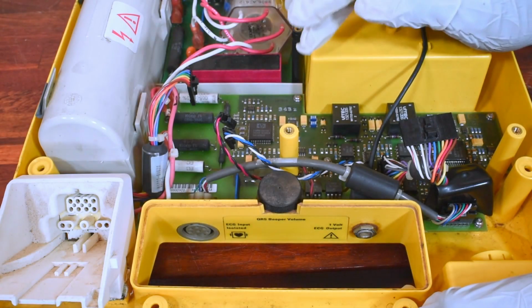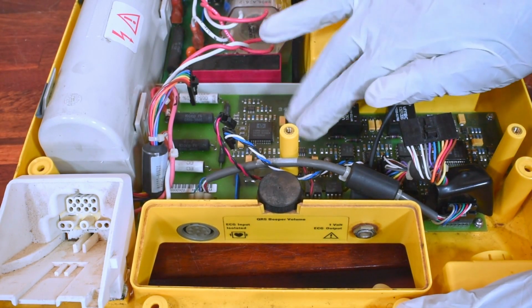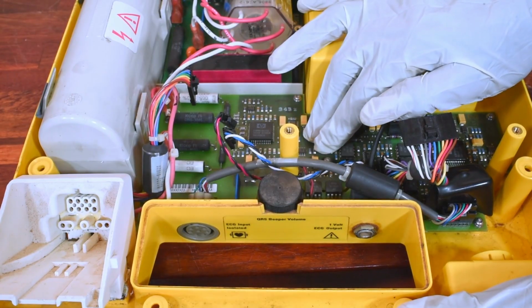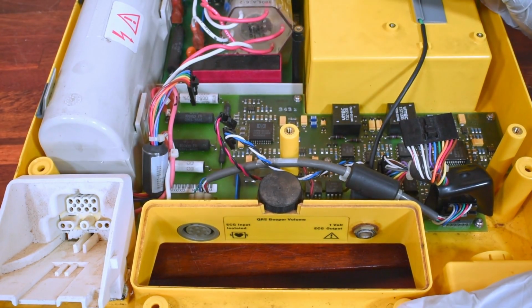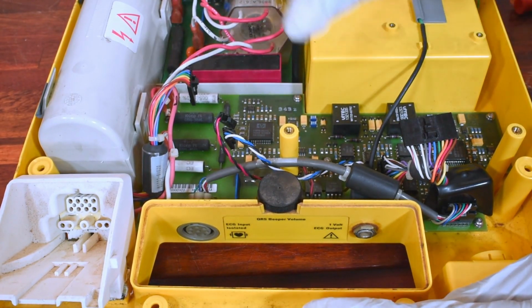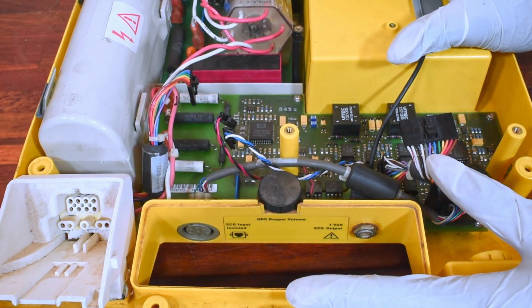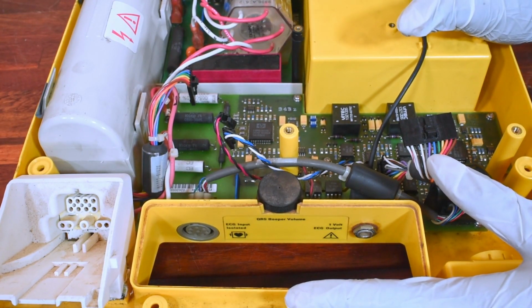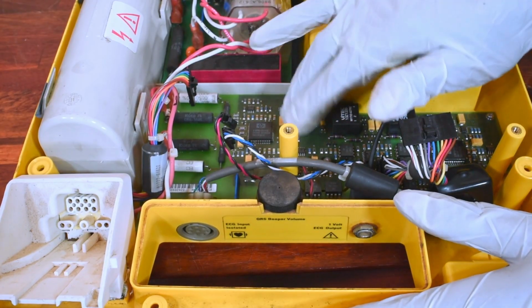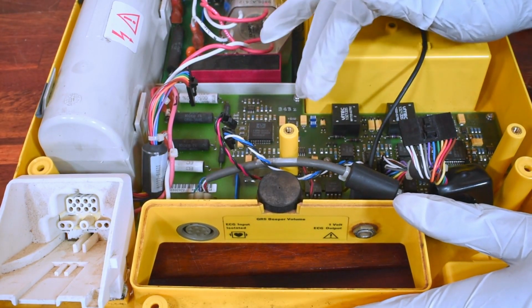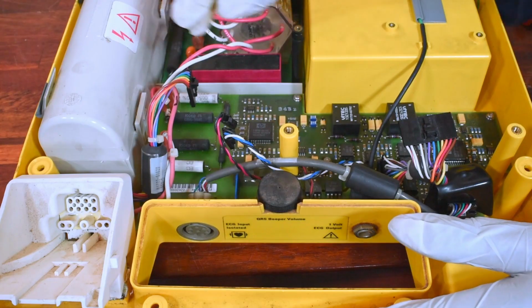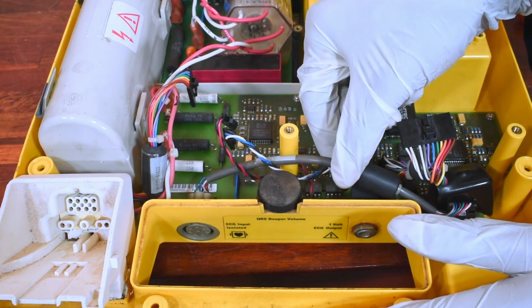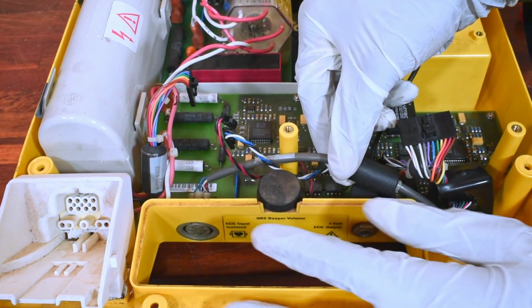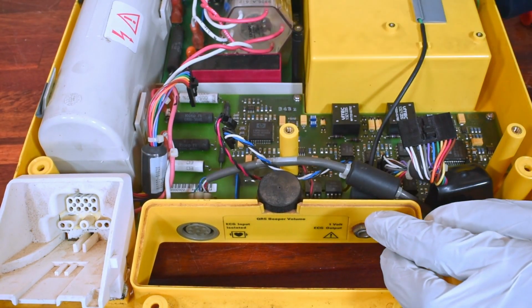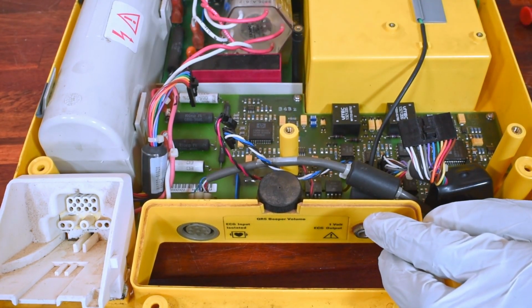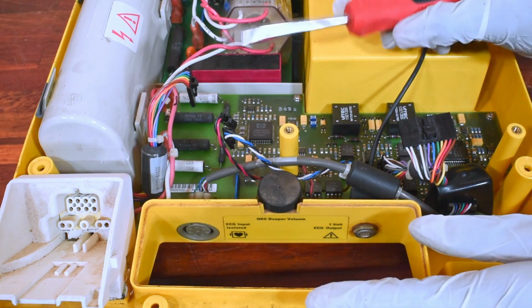As mentioned in part 1 of this teardown video, right here is the ECG front-end control board. Remember that before removing any of these components that you see here, the high voltage capacitor should be discharged. This board can be removed by first disconnecting the wires connected on it and also the cable assembly that runs between the ECG input connector and the board. To remove these wires, you can use a flathead screwdriver to lift up the pins.